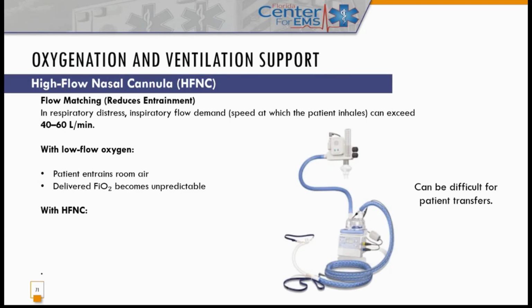The interesting thing about that blender, and it's really hard to tell in the picture, is that at the bottom of the blender, which is at the top, there's a filter there. They're using what they call, and it's by a company called MaxTec Venturi, I don't work for them, so that's my disclaimer, you're able to do that without having medical air in your transport unit. In a hospital, they have oxygen, medical air, suction all lined up on the wall. This one is going to entrain room air from the environment, filter it, and it's hooked up to oxygen. That's how they can use a blender.